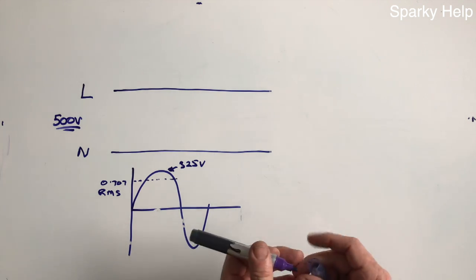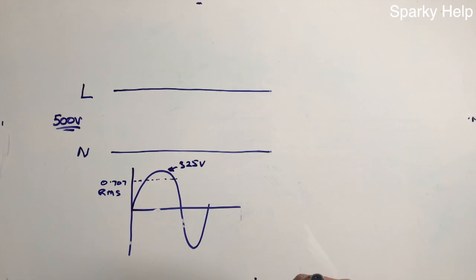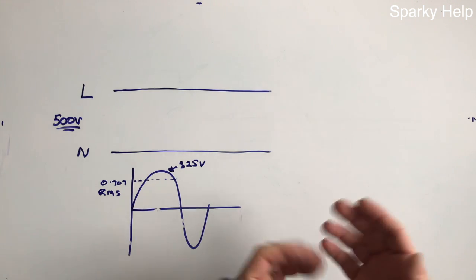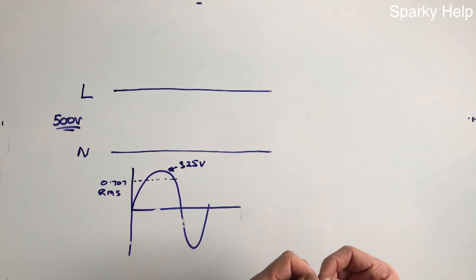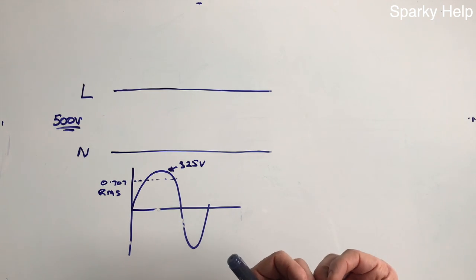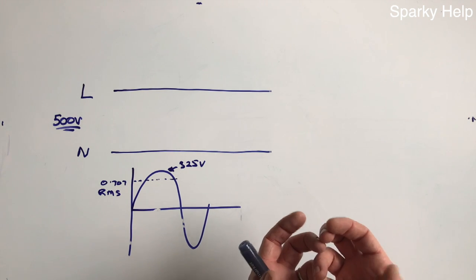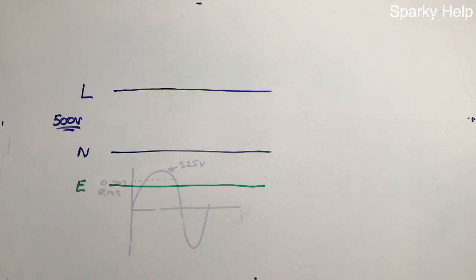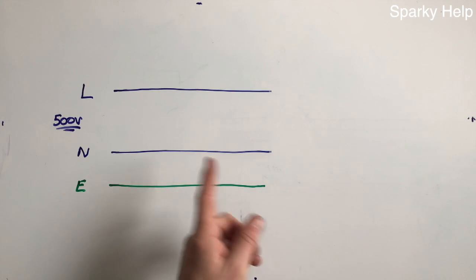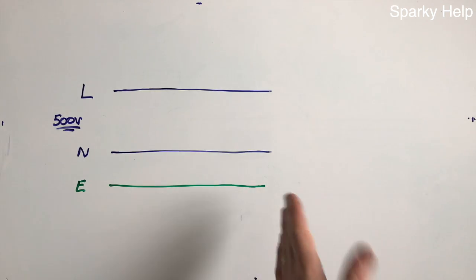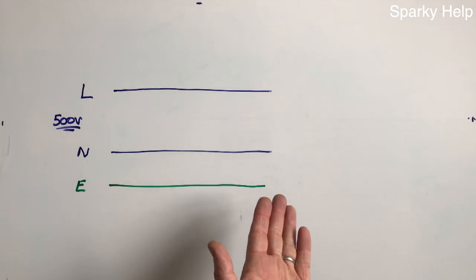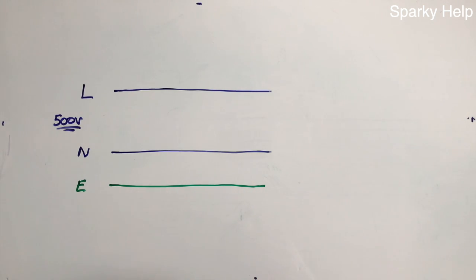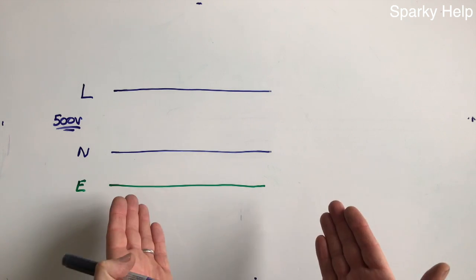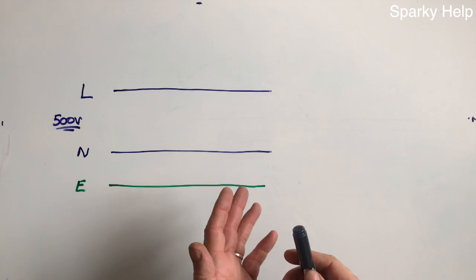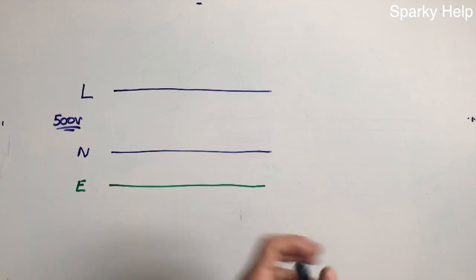The analogy I always give, if people go test lifts and test cranes and things, if it's supposed to carry 8 people, they don't ask for 8 volunteers, they'll load it with whatever the maximum weight is, but they'll go beyond that maximum weight to test whether it actually carries it safely. So here is our circuit. We're going to test it at 500 volts, and we're testing between all live conductors and earth. As we've said, we remove all loads from the supply, so we don't want to test them, basically. So making sure everything is fixed back, nothing is connected, all switches are in the on position, and obviously power is isolated. This is a dead test.